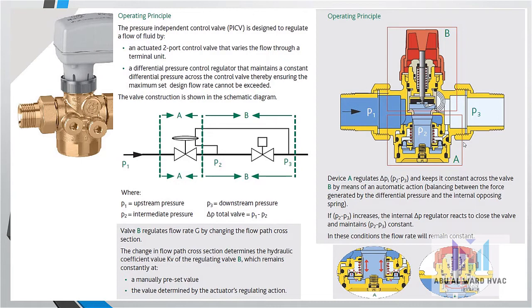Valve B regulates flow rate G by changing the flow path cross section. The change in flow path cross section determines the hydraulic coefficient value kV of the regulating valve B, which remains constant at the manually preset value, the value determined by the actuator's regulating action. Device A regulates delta P1, which is P2 minus P3, and keeps it constant across valve B by means of an automatic action balancing between the force generated by the differential pressure and the internal opposing spring. If P2 minus P3 increases, the internal delta P regulator reacts to close the valve and maintain P2 minus P3 constant. In these conditions, the flow rate will remain constant.